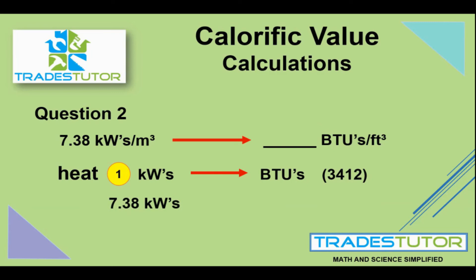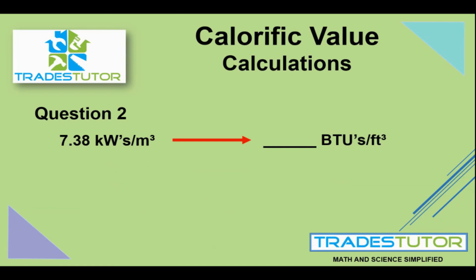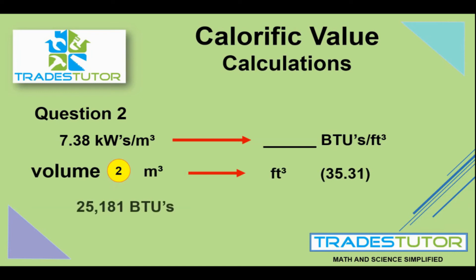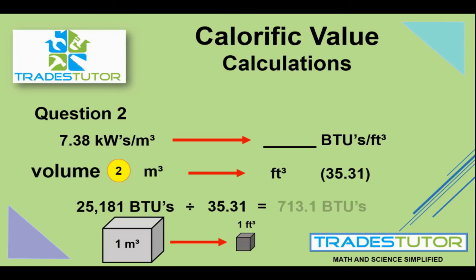We'll take 7.38 and multiply it by 3,412 because it's going to be a bigger number — more BTUs in a kilowatt — to give us 25,181. Don't forget, that's per cubic meter. Step two: cubic meter to cubic feet. We are going smaller, so we divide because a cubic meter is much bigger than a cubic foot. We end up with 713.1 BTUs per cubic foot, which is another way to express the calorific value of a gas that can also be expressed as 7.38 kilowatts per cubic meter.